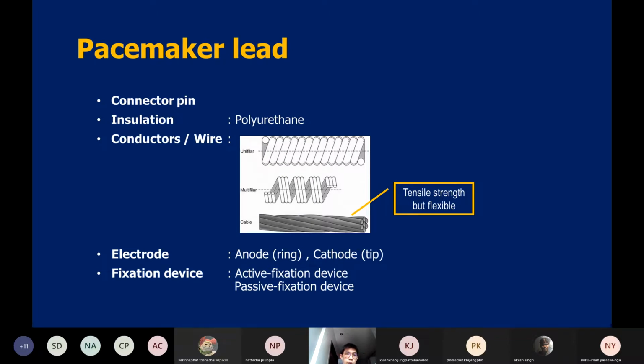So, the pacemaker leads. These are the parts of the pacemaker leads. They have a connector pin, which connects to the pulse generator via the channel that I spoke about before. There's insulator outside the leads to prevent injury to the leads, and there is a conductor, or wire, inside the leads to conduct the electrical signal from the pulse generator. This conductor wire must have the tensile strength to be flexible with the cardiac cycle or the patient's movement, to prevent fracture of the conductor or wire.